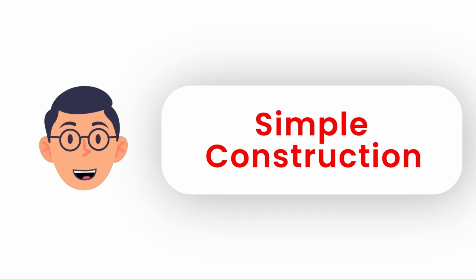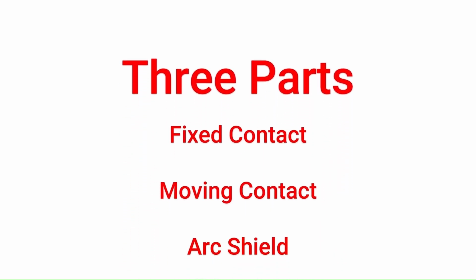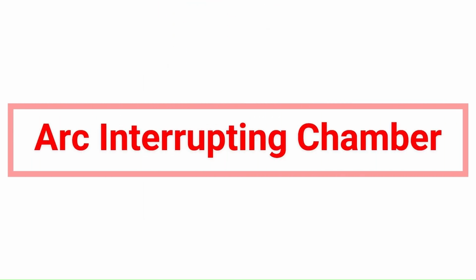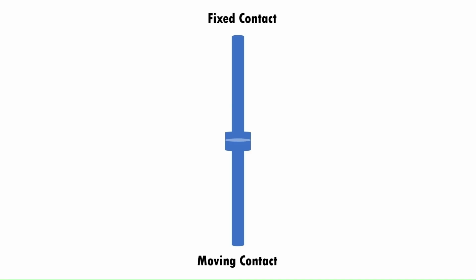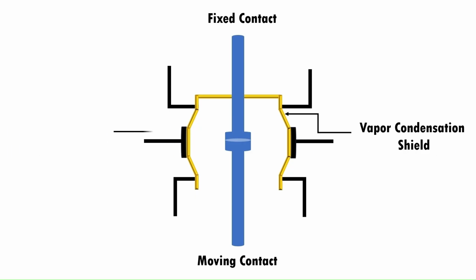It is very simple in construction as compared to any other circuit breaker. Its construction is mainly divided into three parts: fixed contact, moving contact, and arc shield, which is placed inside the arc interrupting chamber. The fixed and moving contacts of the breaker are placed inside the arc shield. An arc shield is a component that prevents metal vapor coming out from the arc on the outer insulating envelope. Therefore, it is also called as vapor condensation shield.